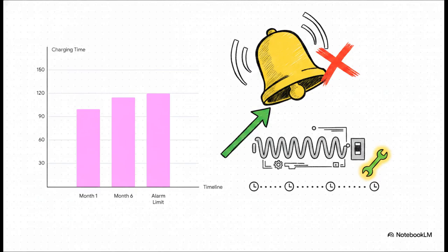Notice the gradual 15% increase in charging time over 6 months right here. If you just wait for the alarm bell to ring, you miss the entire story playing out right in front of you. The much smarter, far more proactive approach is trending the data over time. If you see a spring charging time slowly creeping up, like that 15% increase over 6 months, that is a glaring maintenance signal. It tells you the energy storage mechanism is degrading right now, giving you the chance to fix it long before it crosses a hard limit and delays a critical trip.